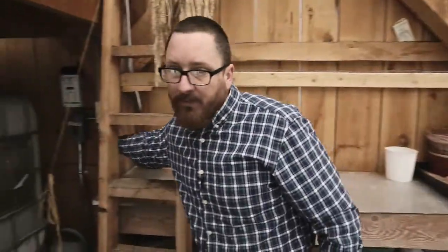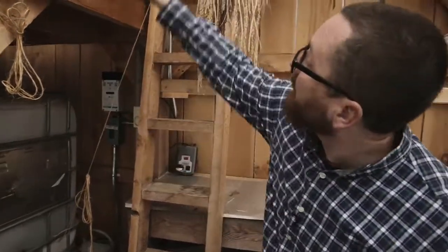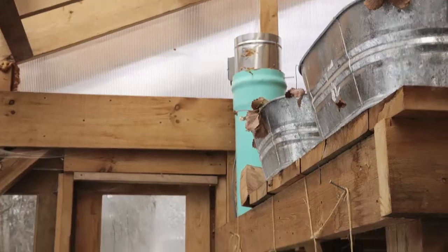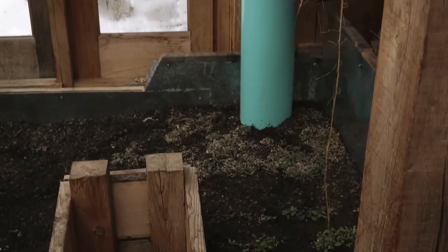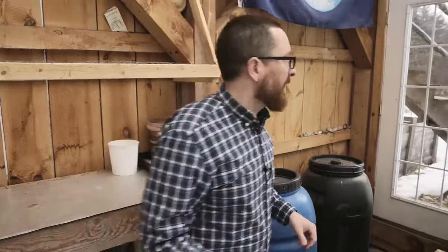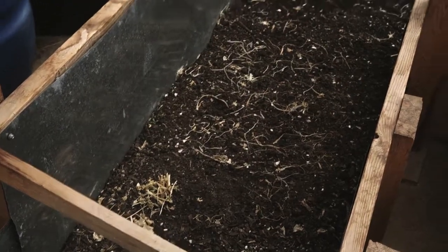One of the things you find with a greenhouse is that you can get excess heat pretty quickly if the sun's out. So what we've created is something we call a climate battery. There's a thermostat down here closer to where the plants are and one way up there. The thermostat triggers a fan at the top of that green pipe and it draws that excess warm air down through the pipe, out through little holes into the sand below our feet. Then it exhausts cooler. The idea is you take excess heat during the day and you bank it in the ground like a battery.